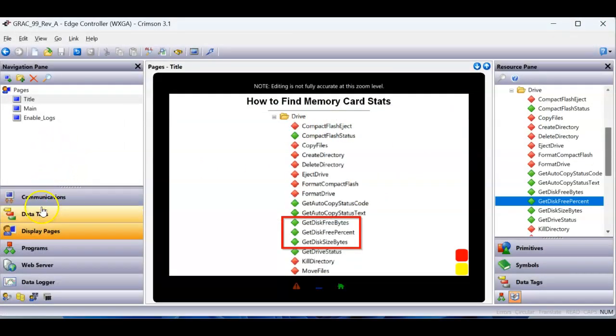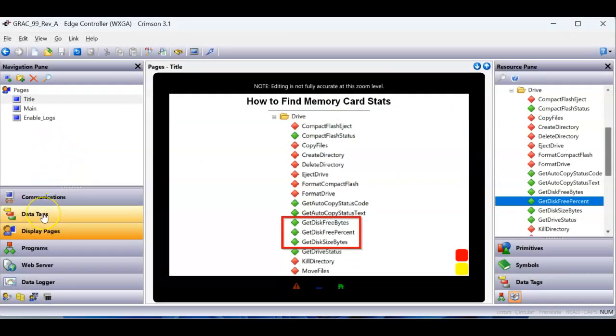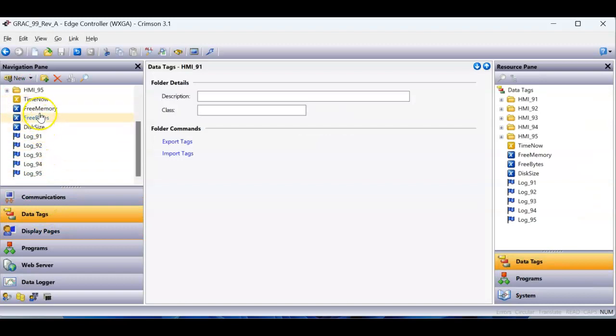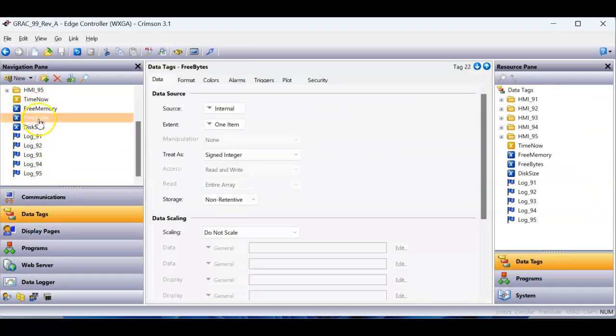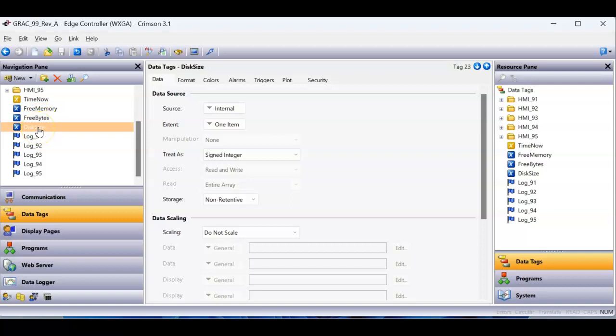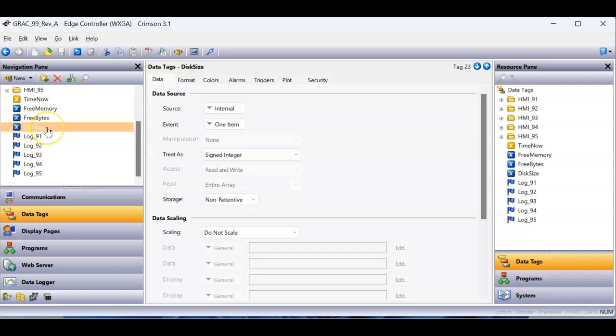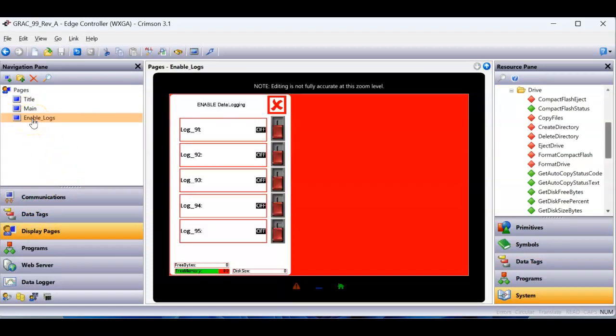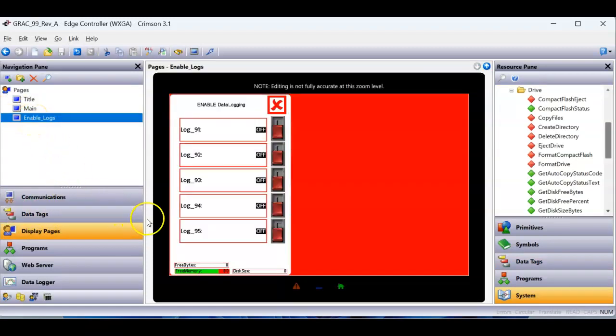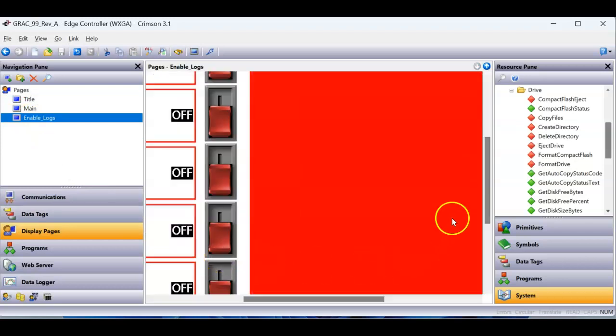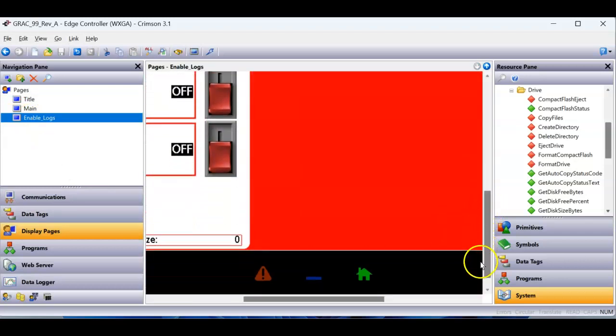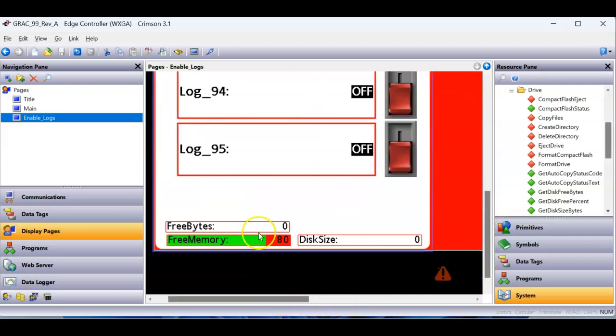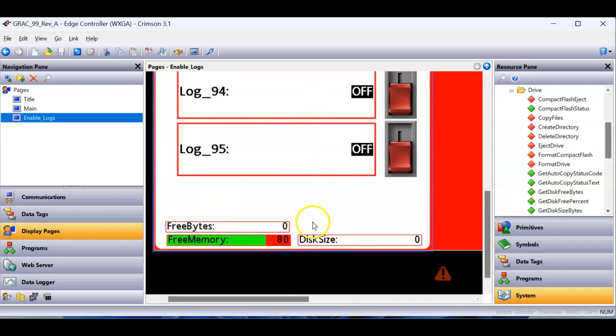So what I did here is I've got over here in data tags, I just created three tags that are nothing more than internal. They're just integers called free memory, free bytes, disk size. And then on my display pages, I created a little pop-up, which is this page here, and on that pop-up, I put those tags down here in this area.